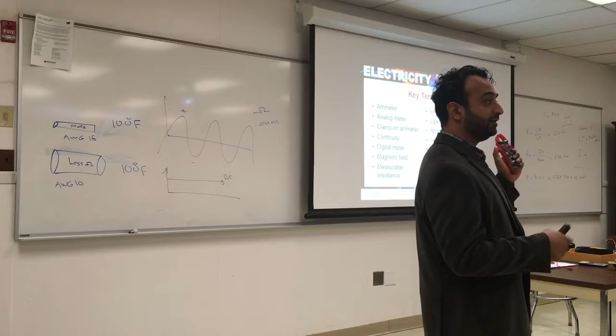Why do we need that in the field? In case you have to put the AC unit about 100 yards from the house, with no place on the roof, so you put it on the first floor and have to run wire all the way to the third floor. Or maybe the control panel is in the basement and you have to run it up to the first floor. You have to measure the resistance of the wire, per foot, before you do the run. Either you measure it, or sometimes it's labeled on the wire.